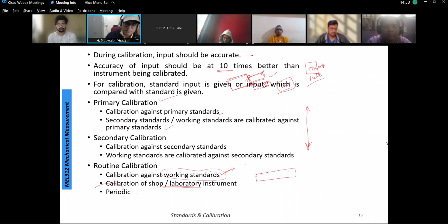Okay, so calibration of the shop or laboratory equipment or instrument is to be done with something that is preserved at a good place in a controlled temperature, pressure, and other conditions, which is to be done periodically, right? So there are now methods called direct calibration. Obviously, there will be one more called indirect calibration, right? So direct calibration is one with the known input sources. Say for example, flow meter.